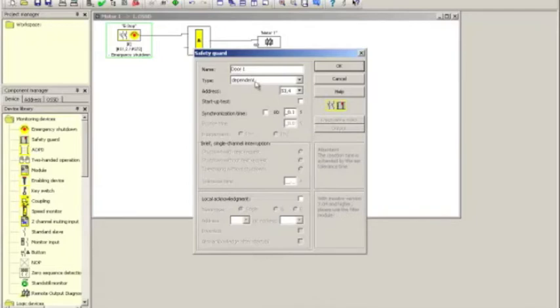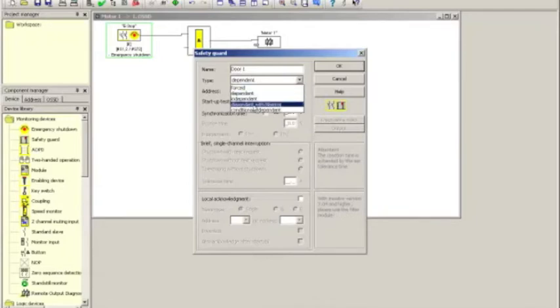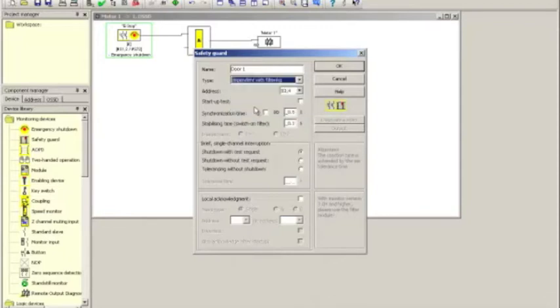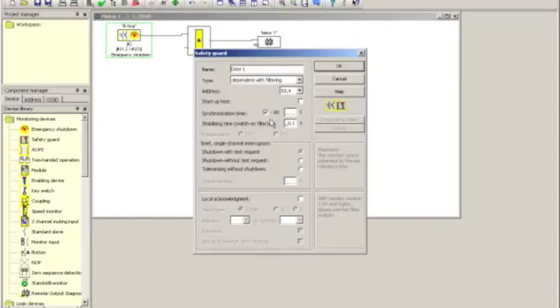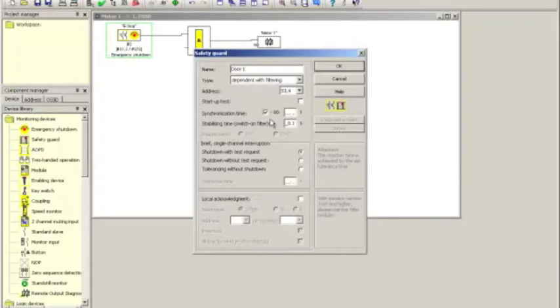I will configure the magnetic door switch also as a dependent with filtering, but I will make two changes. The first change is I will check off the infinite synchronization time. What this allows to happen is when a door is closed very, very slowly, the magnet can pull in the first contact on the magnet switch and much, much later the second contact without causing a fault.